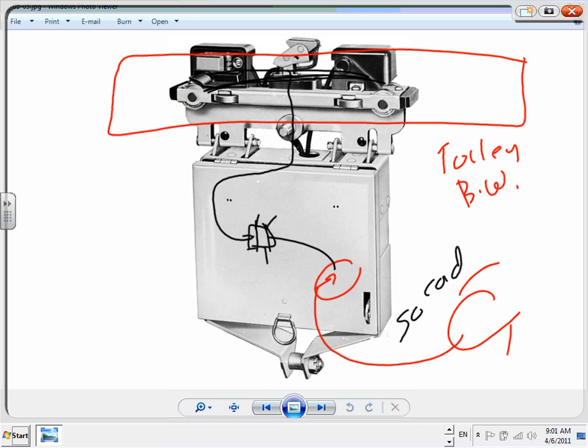And then a fuse, why do we have a fuse? With 3 conductors of number 12, I need a 20 amp fuse, because this busway happens to be 225 amp. So from the 225 amp, I'm tapping and feeding a 20 amp fuse, out of the fuse a receptacle, and out of the receptacle a plug that goes all the way to feed the machine. What's the advantage of this? You can drag it along a predetermined path, which allows you to do a function, build a car, butcher a cow, or whatever you want to do.